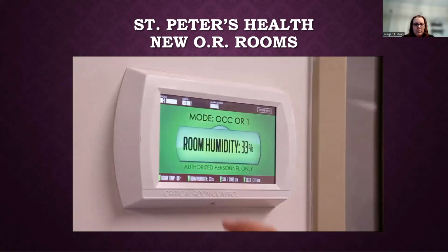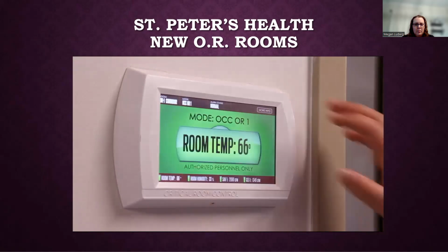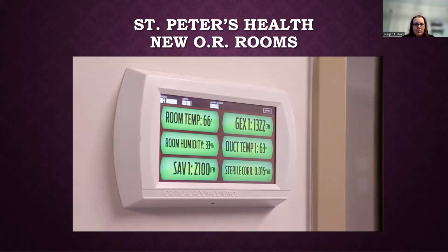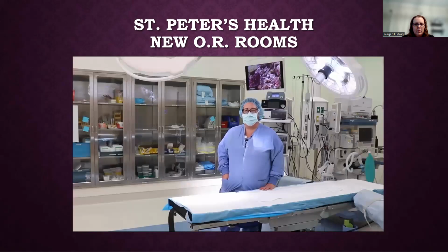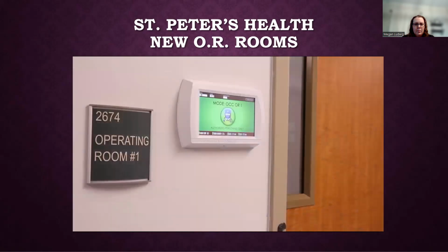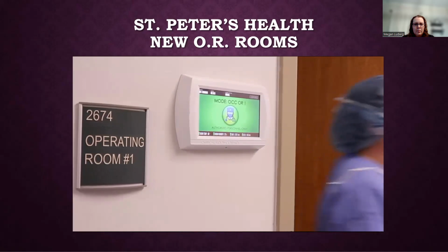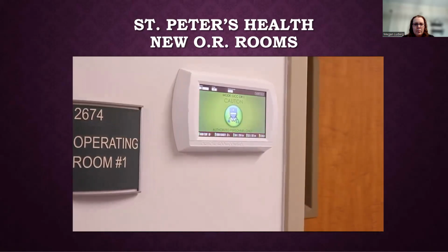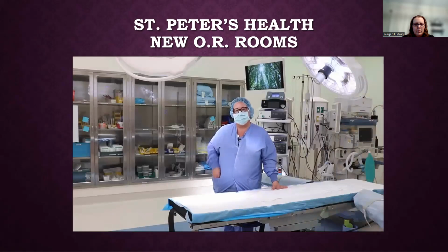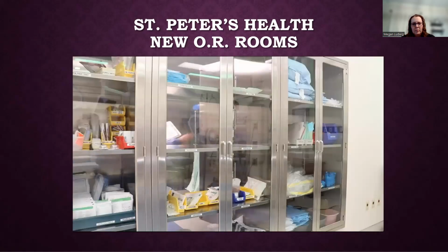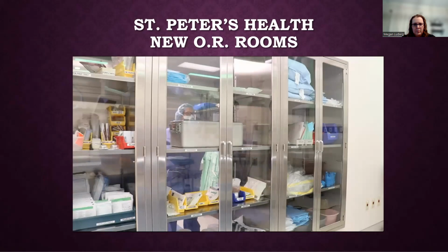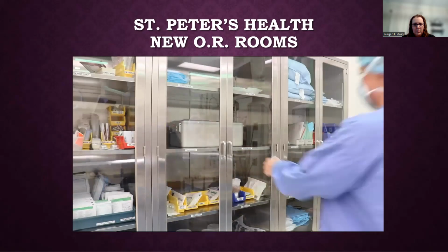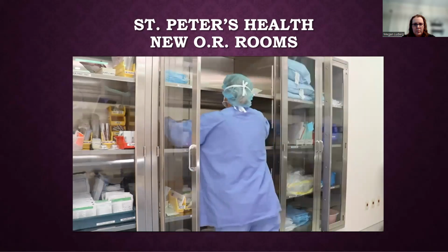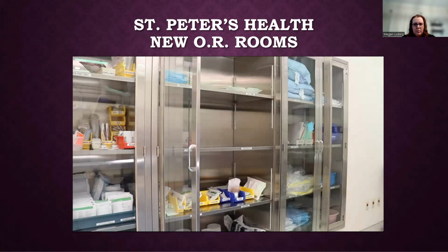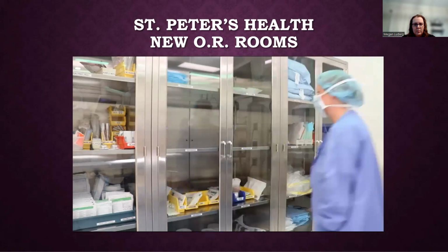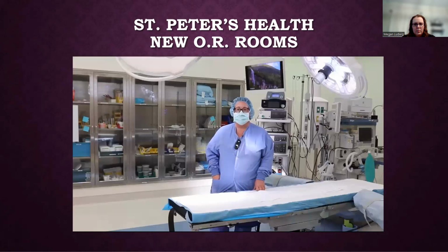These smart readers in the room are able to tell us what our airflow is, the temperature, the humidity. We have a new air handler that's able to handle all 6 operating rooms on the same air handler. The positive pressure allows all of the air to move away from the field, so there's nothing that is going to float back into the field. We also have these new pass-through cabinets. If we need additional instrumentation or supplies, we can call out of the room, and a person in the sterile core can come and put an item in the pass-through, close the door, then we can open it from the operating room side and not disrupt the airflow in the OR.